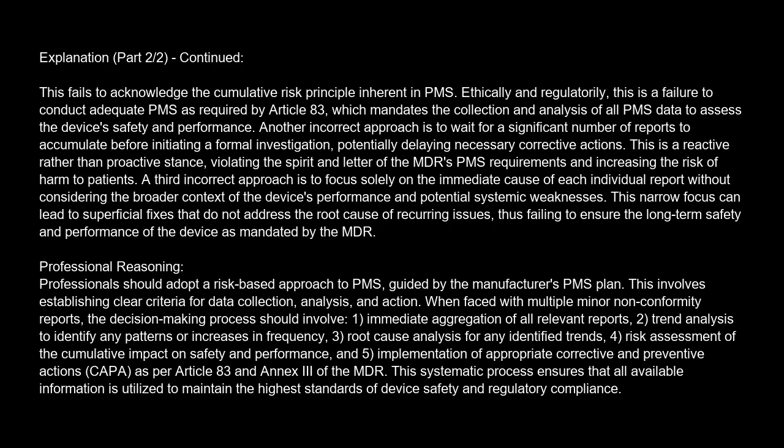Professional reasoning. Professionals should adopt a risk-based approach to PMS, guided by the manufacturer's PMS plan. This involves establishing clear criteria for data collection, analysis, and action. When faced with multiple minor nonconformity reports, the decision-making process should involve 1. Immediate aggregation of all relevant reports.